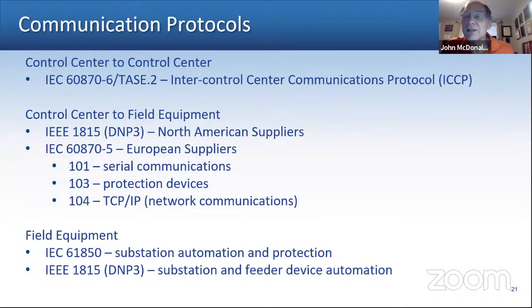What makes it easy today is that if I look at 3 different levels of the grid: control center to control center, where electric utilities exchange information with each other, whether country to country or within a country, one large utility with another. There's one industry standard everybody uses for this, called the Inter-Control Center Communications Protocol, or ICCP. One global standard. From the control center to the field equipment, there are really 2 standards we use, depending on where the supplier is located.